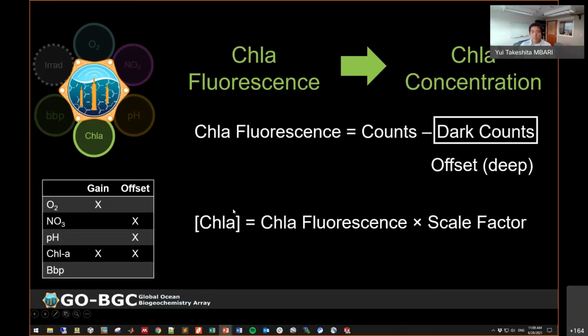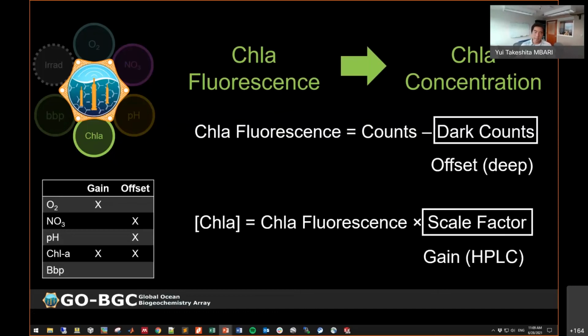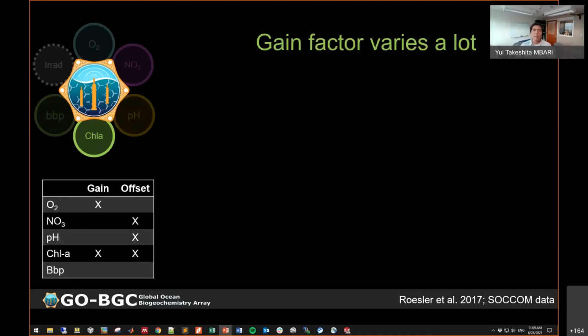fluorescence to concentration of chlorophyll, because we need to multiply this fluorescence against the scale factor. So that's from the gain, and we try to establish a scale factor by comparing sensor measurements to concentration of chlorophyll by making discrete measurements using HPLC. But the problem is that this gain factor is very, very variable.